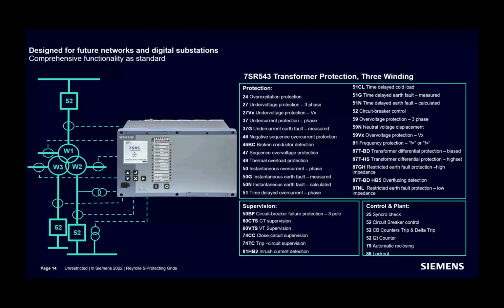This is also available for 7SR42 for 2 winding variants. So you can apply restricted earth fault for each of these windings at the same time individually without disturbing any other. And of course, plus the overall differential protection is in operation. As it is a 3 winding solution, you will appreciate that 7SR543 is available in size 12 casing, our biggest case.